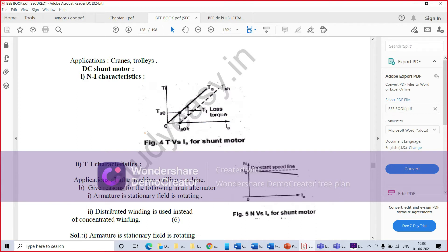The second characteristic is the torque-armature current characteristic. Torque is proportional to flux and armature current. Neglecting armature reaction, flux is constant and torque is proportional to armature current, so the torque-current characteristic is a straight line passing through the origin. From the curve we can see that huge current is needed to start heavy loads, so this type of motor should not be started on heavy loads.